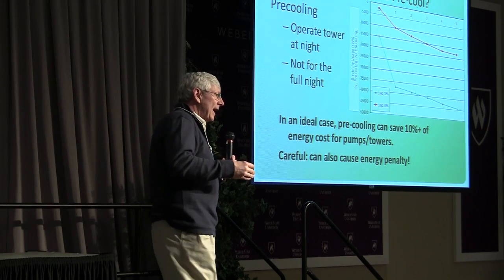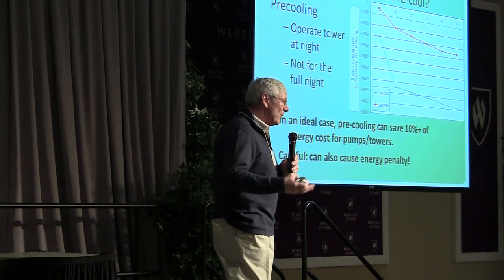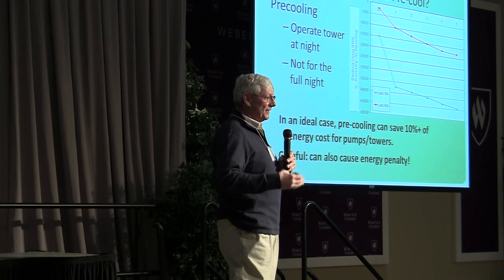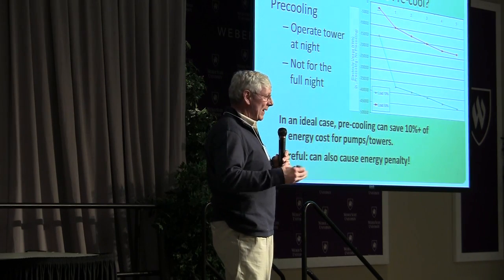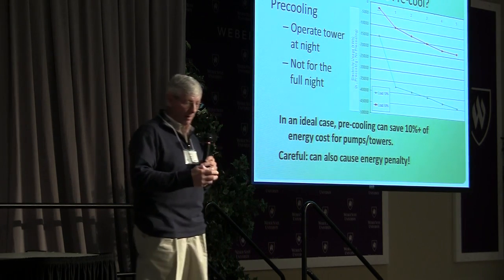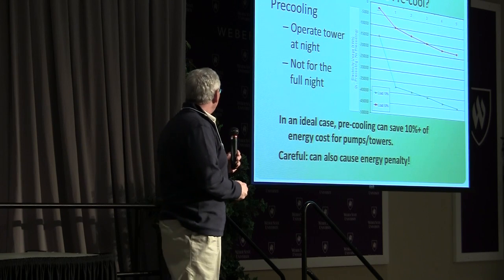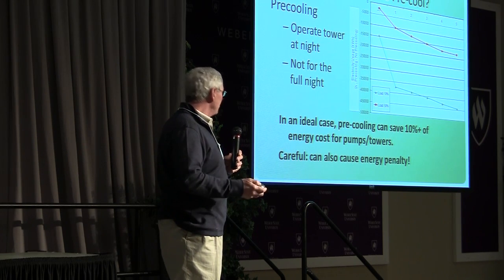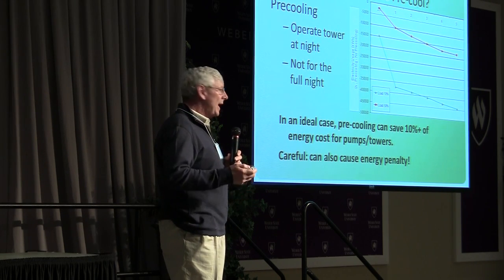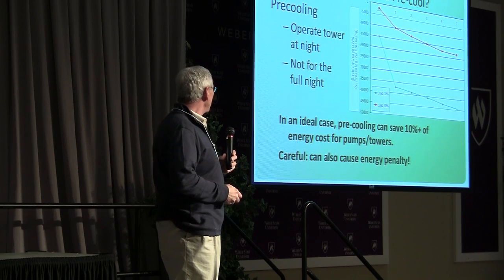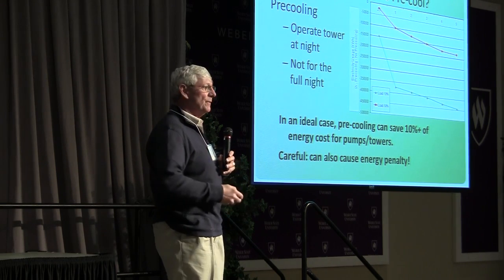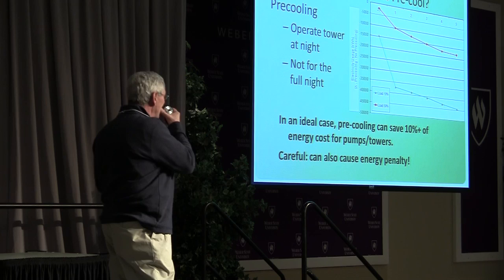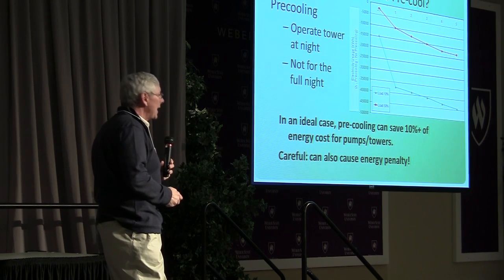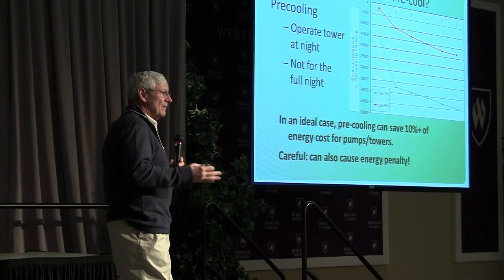Our EERs in that case jump up to somewhere in the neighborhood of 16 to 18 on conventional equipment, and as high as 28 EER on high efficiency equipment. Pre-cooling, used properly and set up at the proper time, is going to save about 10% of the energy cost for pumps and towers. This was verified in a DOE study by Scott Hackle and the Energy Center of Wisconsin.